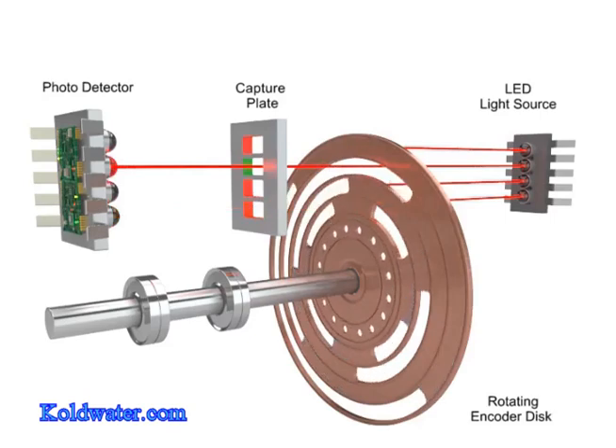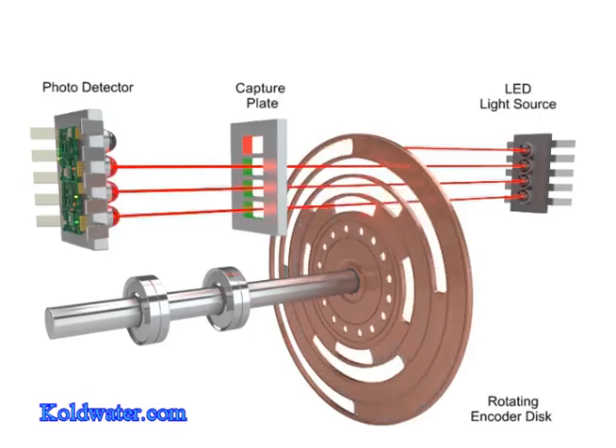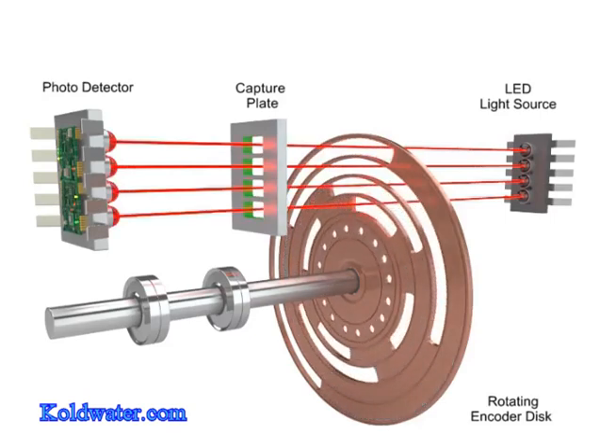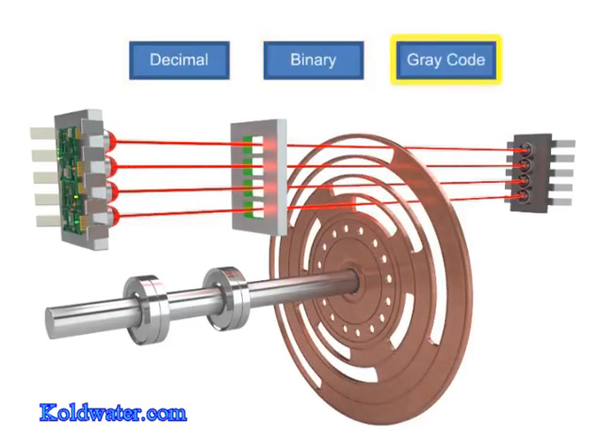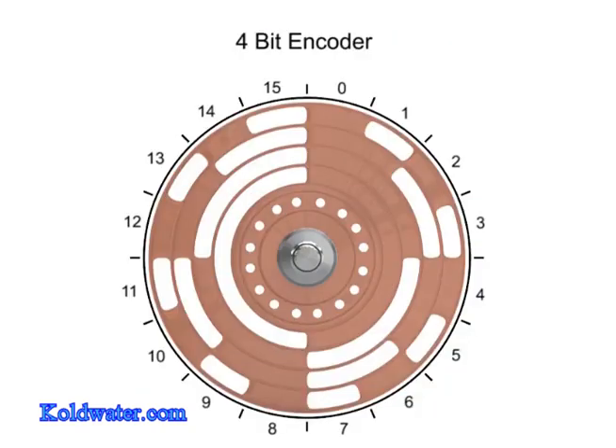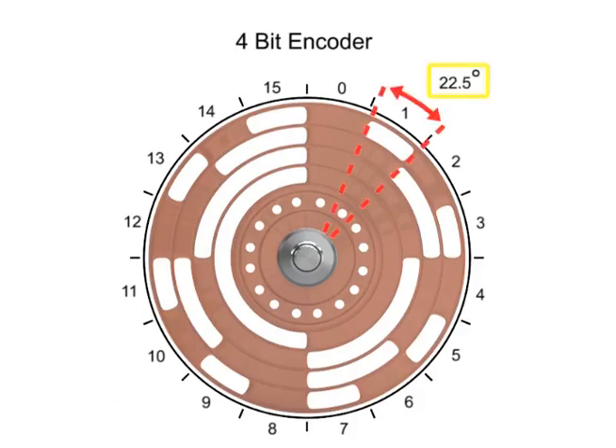The most common types of numerical encoding are decimal, binary, and gray code. In a four-bit encoder there are 16 unique combinations, or numeric codes, every 22.5 degrees.